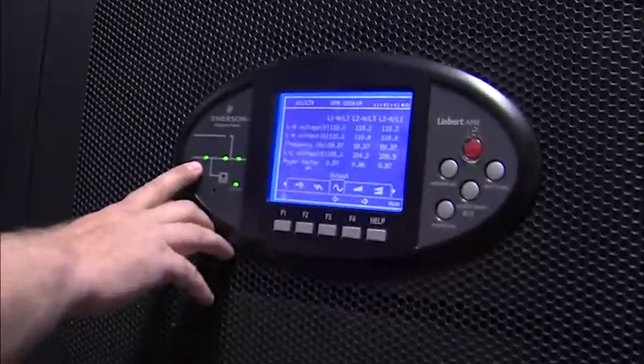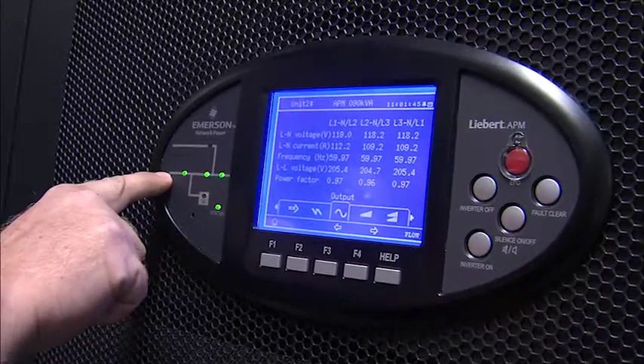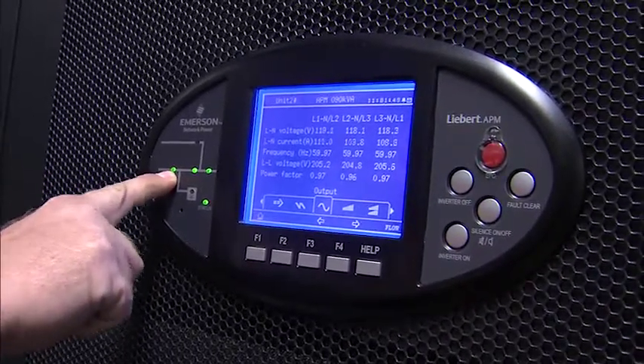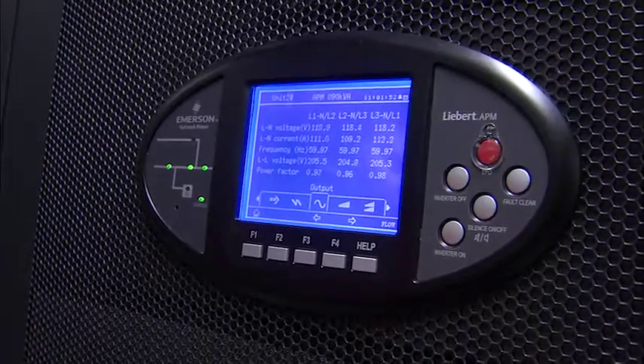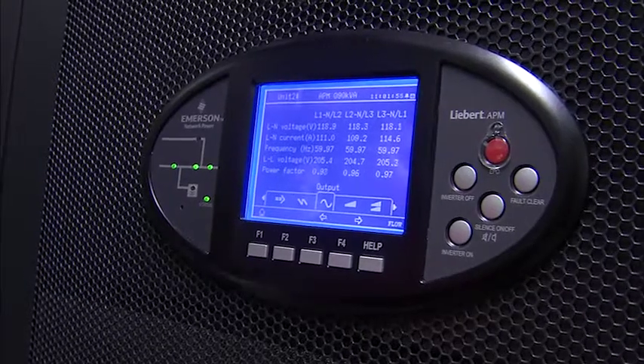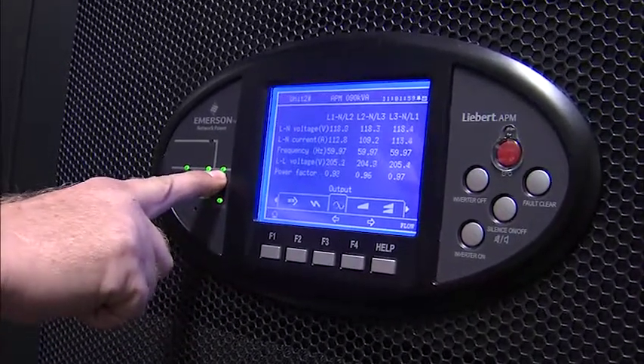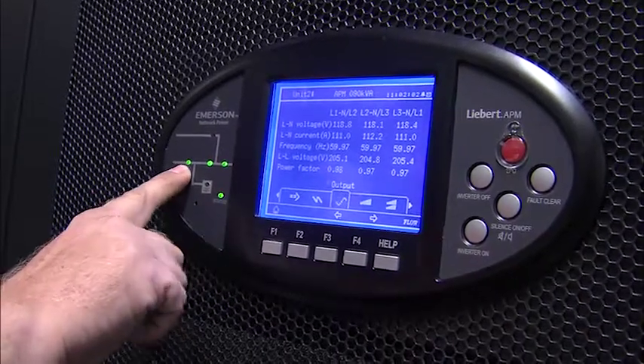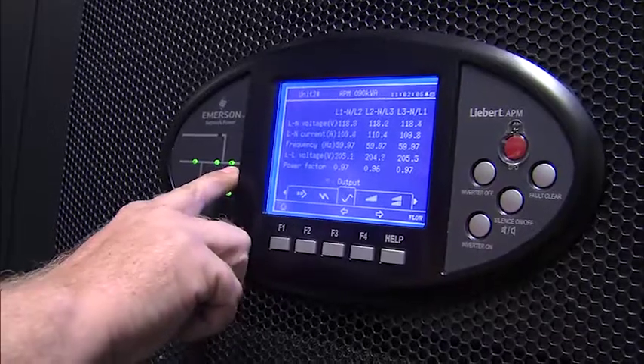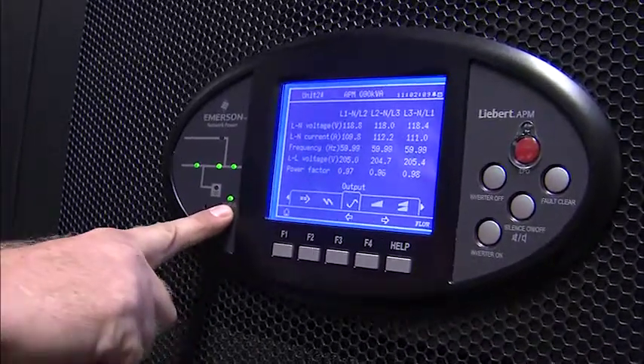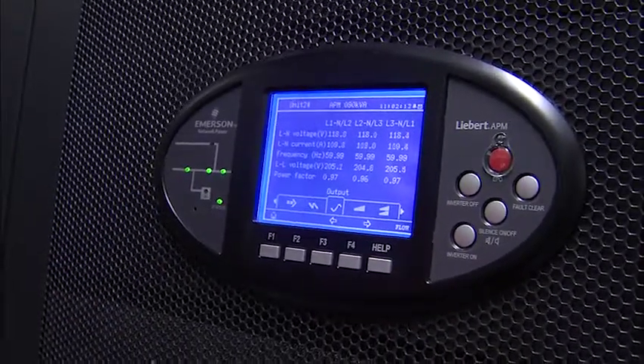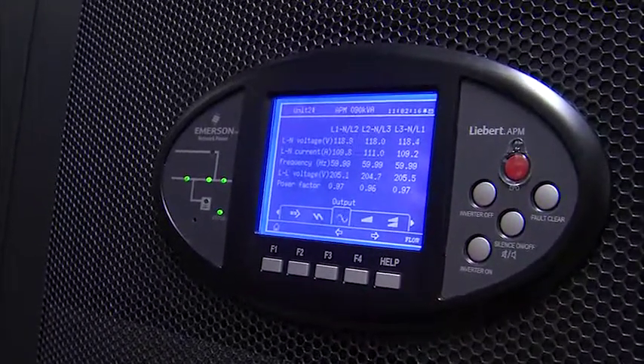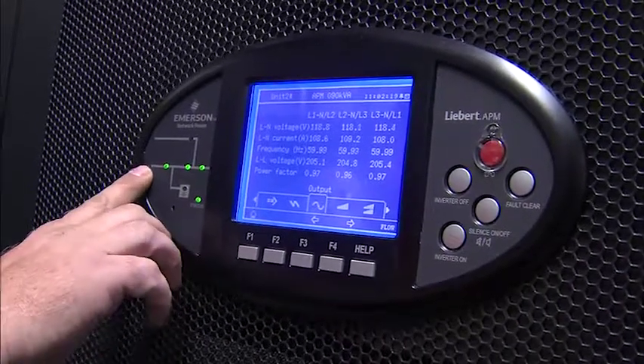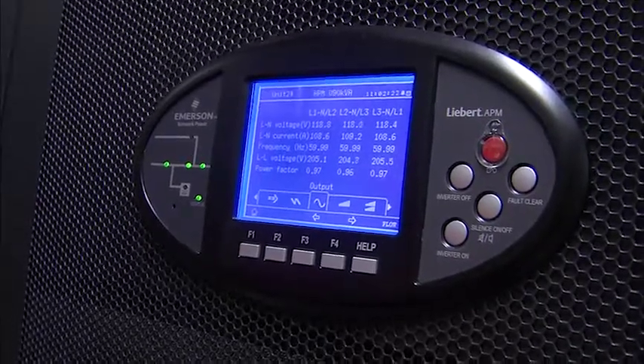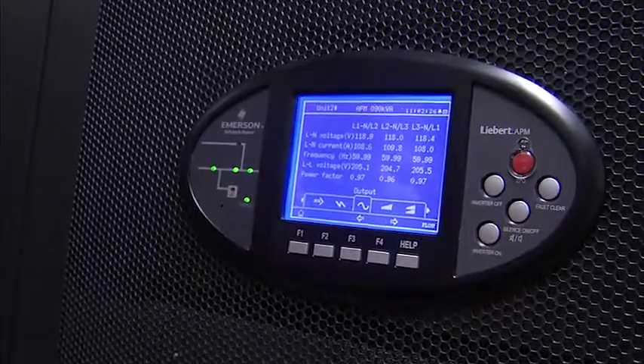Back here, walking through this display, from left to right, we have our power path. So our utility coming in, and it comes in through the input of the UPS, in through what we call the inverter and rectifier. The inverter and rectifier are what cleans the power, and then out through your output. Your output then feeds your load. So when looking for normal operation, we're looking for 3 green lights in a row. Your status is always green unless this changes. And then it will go either red on alert, or if you go into bypass, it will go amber. So again, straight across, all 3 green. If you do physical checks, you want to check them all, just come in and look. All 3 green is good.